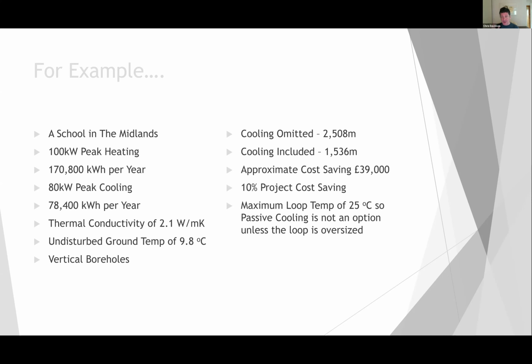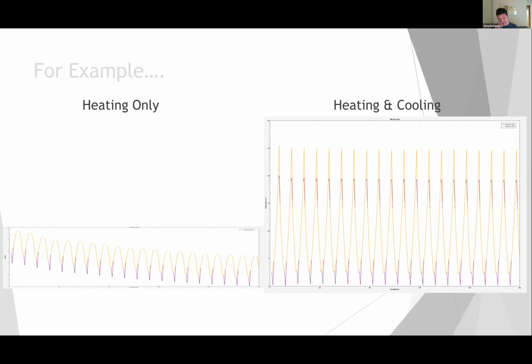So we've got to look at not just the loads on a peak and an annual basis, but we've got to actually model those ground loop temperatures. And again, if I show you the graphs, that's the same graph as before, just the heating only. And you can now see that our summer temperatures are getting up very significantly.